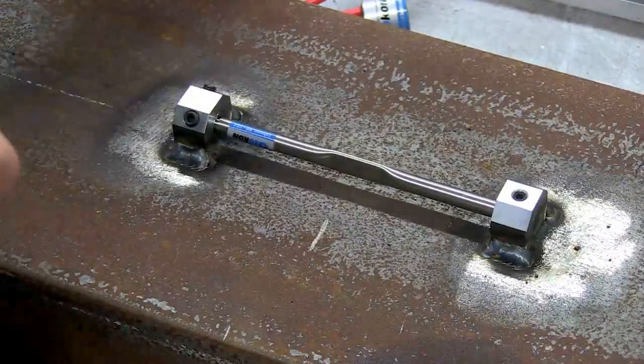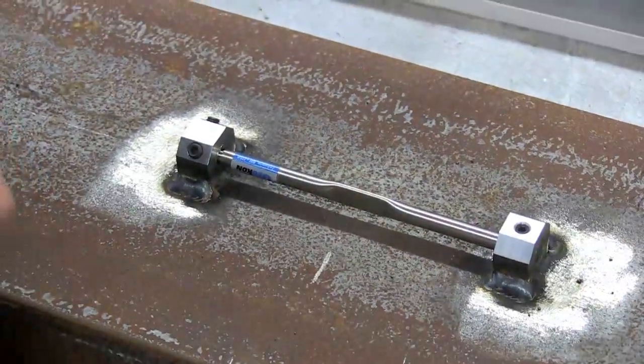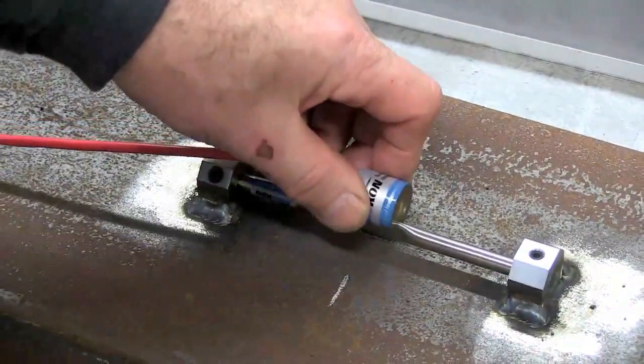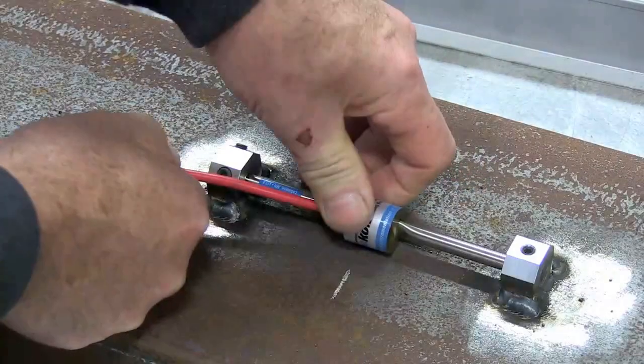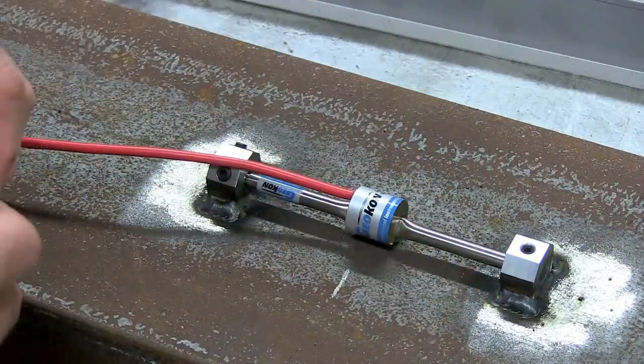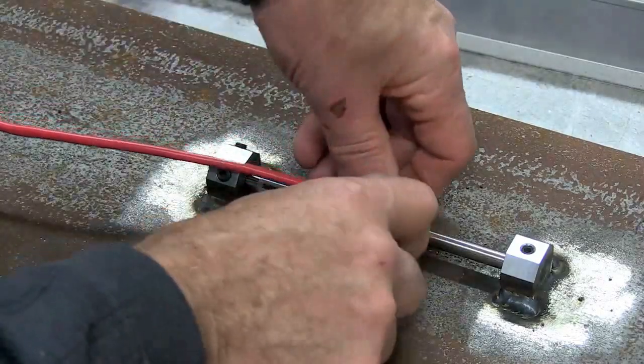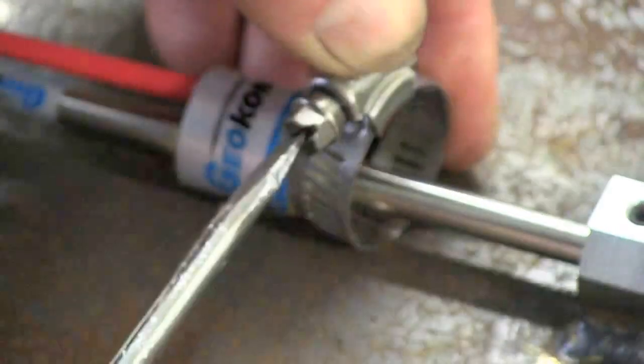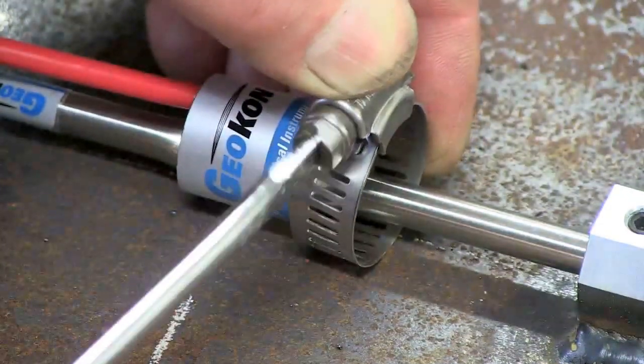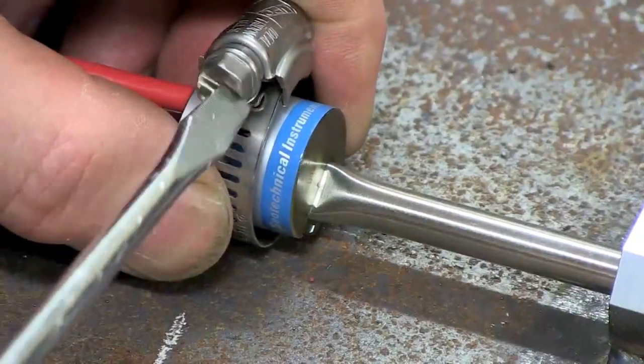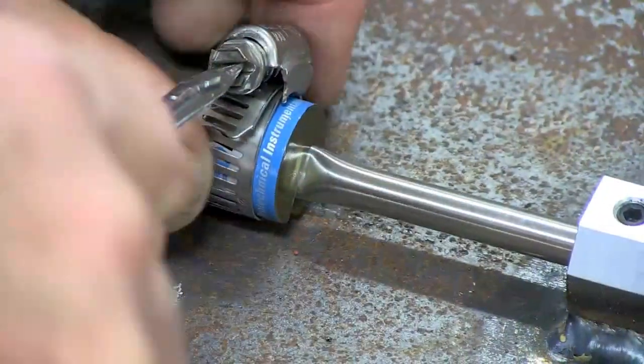Following the tightening of that, we need to install the coil. This tube has a crimp in the center where the coil engages the tube. When we do that, we need to include this hose clamp. Put the coil until it stops at the end of the slot. Open up the hose clamp. Be sure you have the gauge all the way into the slot of the hose clamp. That basically centers the excitation coil. Tighten the clamp.